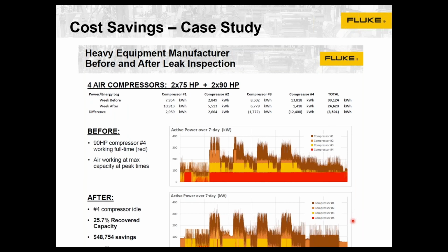After using an II-900 and detecting and fixing leaks, this is what the after looked like. And you can see from the image that really compressor 4, you almost don't need it. So it truly just becomes a backup compressor. So very significant changes there. And this is just a weekly consumption. So you can see a pretty dramatic drop from about 33,000 kilowatt hours down to a little over 24,000. And it also shows a good use of it: if you have the ability to log before and after, you can show direct energy savings costs.